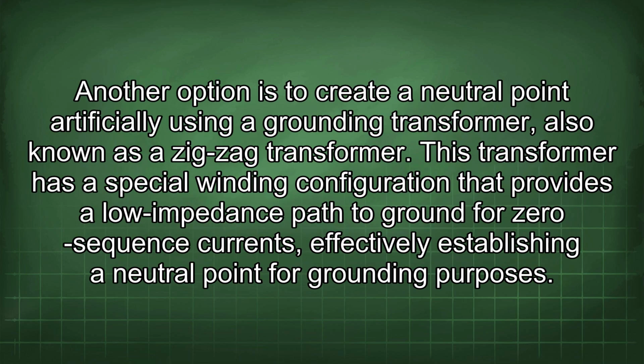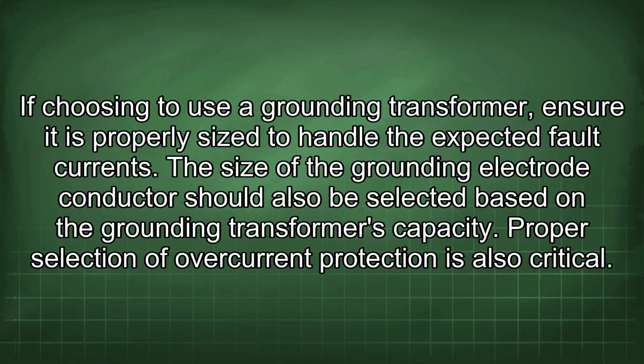Another option is to create a neutral point artificially using a grounding transformer, also known as a zigzag transformer. This transformer has a special winding configuration that provides a low impedance path to ground for zero sequence currents, effectively establishing a neutral point for grounding purposes. If choosing to use a grounding transformer, ensure it is properly sized to handle the expected fault currents. The size of the grounding electrode conductor should also be selected based on the grounding transformer's capacity.